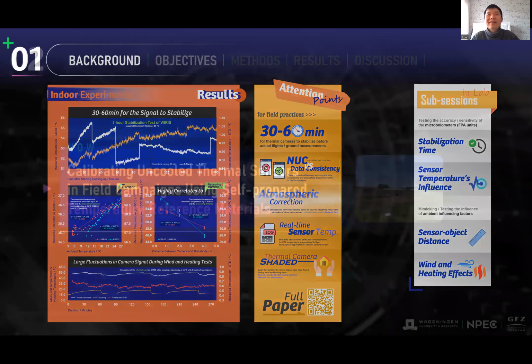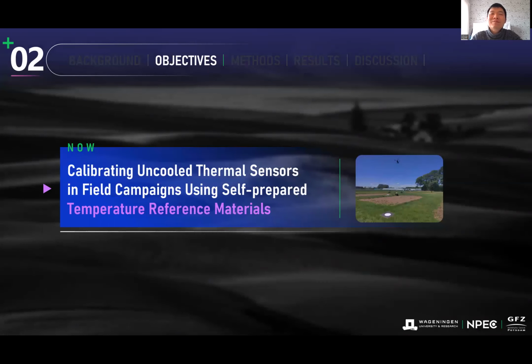That finishes my indoor part, and now we can move to the outdoor part of the thermal sensor calibration. In this part we introduced different targets. In the indoor experiments we used the black body as a target, and now we have used several self-prepared temperature reference materials for calibration outside.